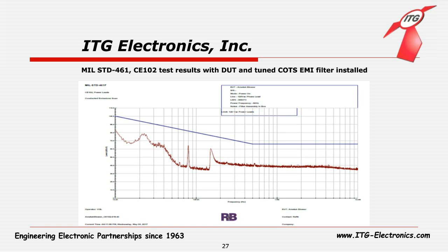Amy is asking, during the tuning, how are you adding components to the sealed unit? Are you adding them in series with the existing filter, I'm assuming? Right. If it's an additional component, for example, the differential mode inductor, we were able to add it externally. But increasing the component values, then we have to make a prototype. We have to make a prototype in order to increase the common mode inductor values.